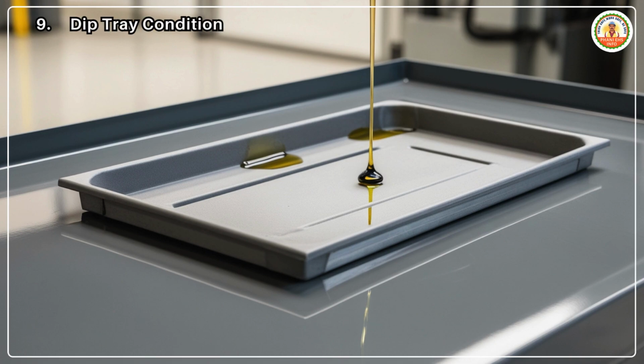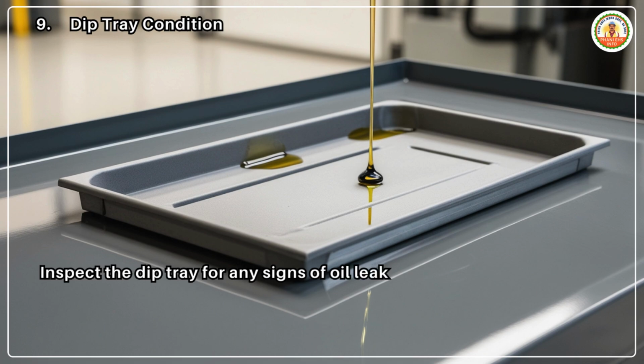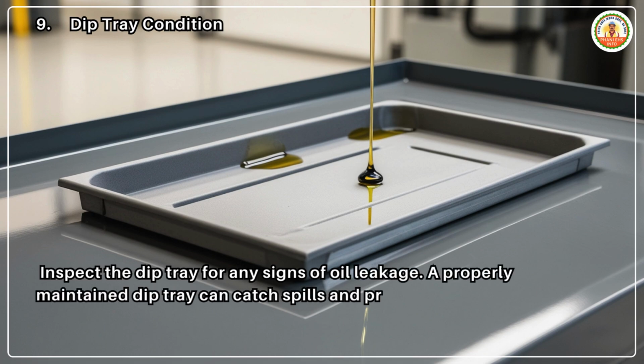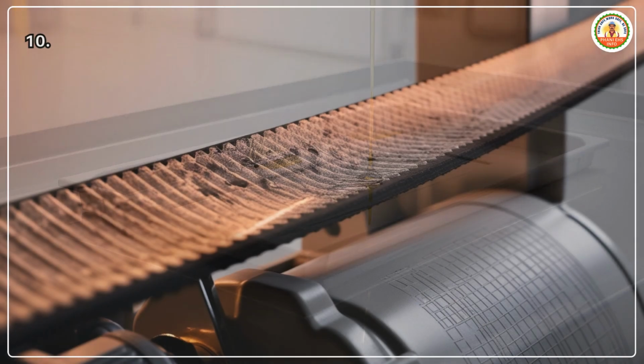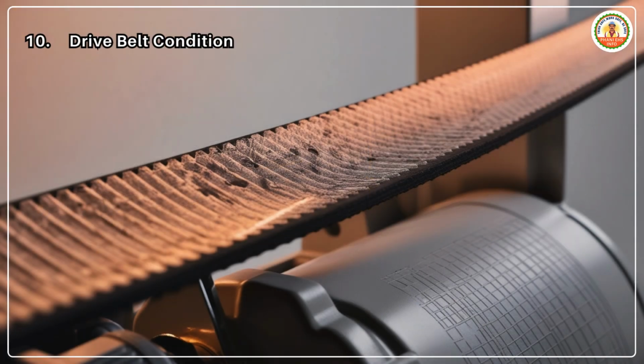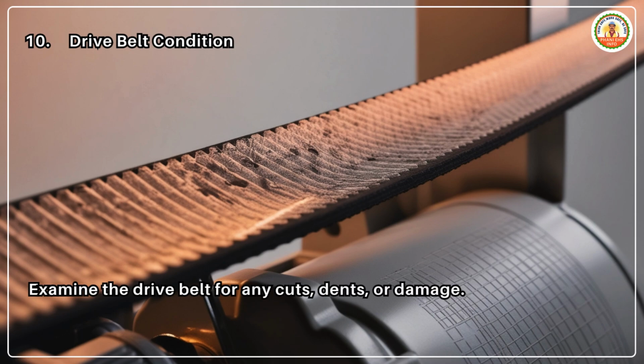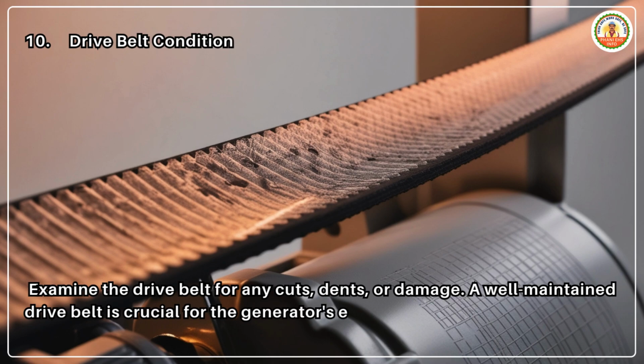9. Dip tray condition. Inspect the dip tray for any signs of oil leakage. A properly maintained dip tray can catch spills and prevent environmental contamination. 10. Drive belt condition. Examine the drive belt for any cuts, dents, or damage. A well-maintained drive belt is crucial for the generator's efficient operation.